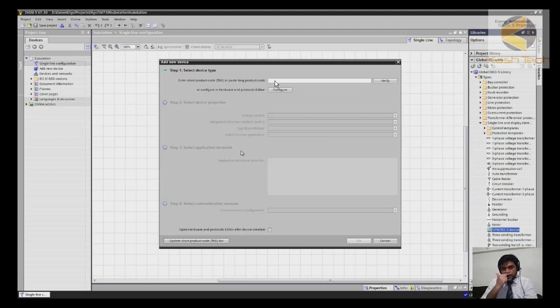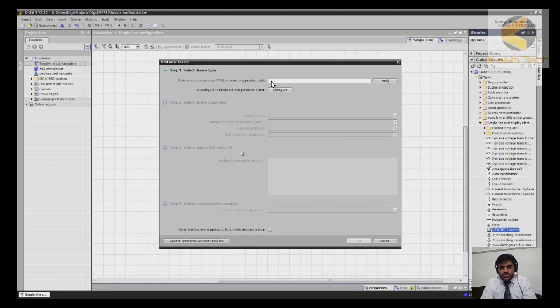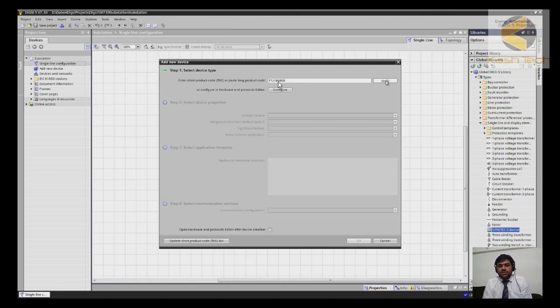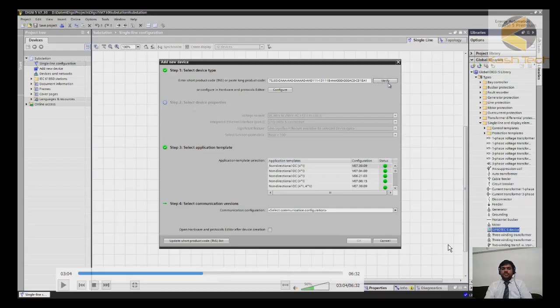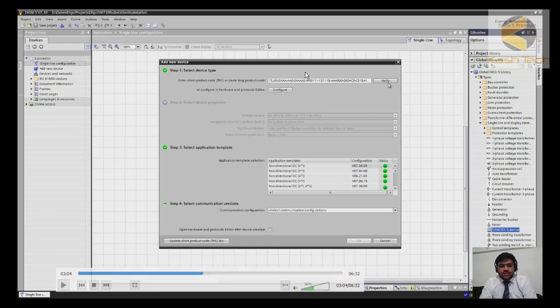Once you drop it, a dialogue will open. At the top you have to enter the product code of the device. There are two types of product code: a shorter version and a longer version — you can find it on the label of the relay or from the ordering information. You can also get the short code using a tool called the Online Configurator by going online with the device. Once entered, click Verify and DIGSI 5 will check and validate the product code.